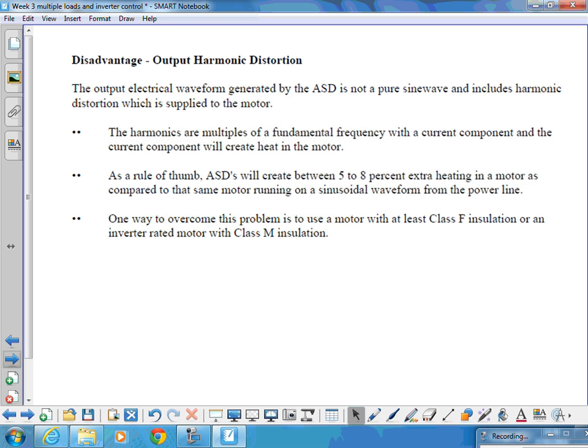So they're multiples of the fundamental frequency. Any waveform can be said to be made up of a fundamental and a number of harmonics. These harmonics can cause a current component, and a current component will create heat in the motor. So we've got extra harmonic currents flowing, and then we've got this issue that if we get a resonance with one of the harmonics, we can get some big voltages or large circulating currents set up. So they aren't a good idea.